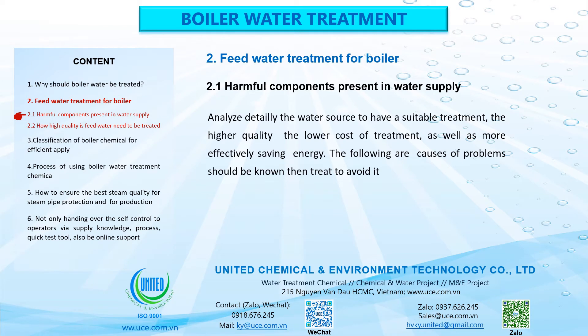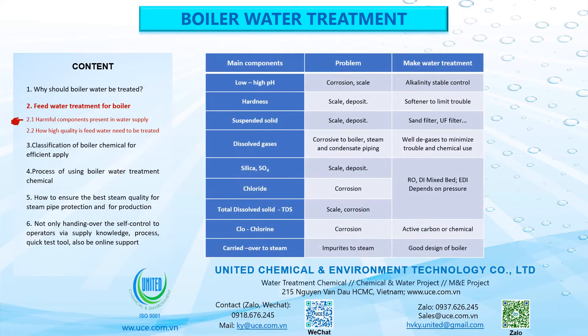2. Feed water treatment for boiler. Harmful components present in water supply should be analyzed in detail to have a suitable treatment. The higher the quality, the lower the cost of treatment, and the more effective the energy savings. The following causes of problems should be known and treated to avoid issues. 1. Main component: Low or high pH. Problem: corrosion and scale. Water treatment should include alkalinity stable control.